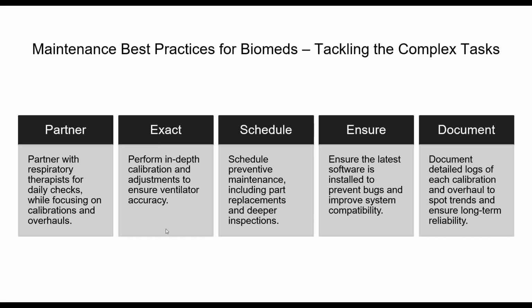Some ventilators you'll do the calibration for pressure, then for flow, then for volume. Now pressure, if you adjusted it first, can be counter adjusted - it can go off just a little bit, still probably within tolerance, when you adjust the flow and volume. Go back and redo it - it tightens things up, you get everything in a tighter spec. That applies to some ventilators, not all.